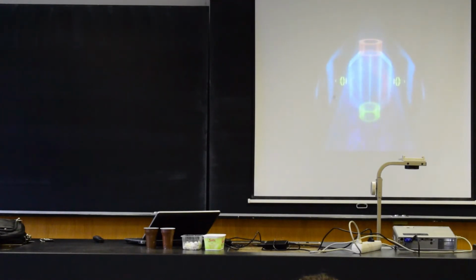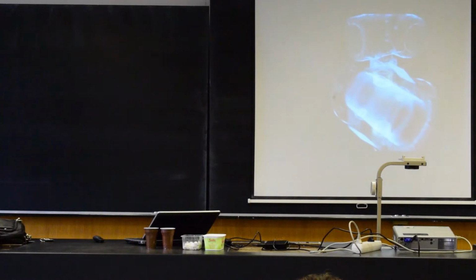For example, electrochemical effects in the liquid, or external electromagnetic fields. Thus, the size of such interference voltages has no impact whatsoever on the actual measuring signal. The advantages of this are a stable measurement and a stable system zero point.